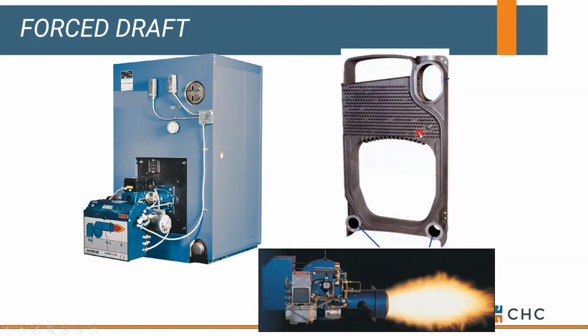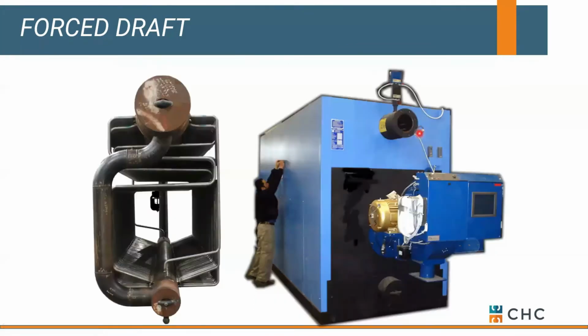You could take that same power burner and stick it into a steel tube design. So this is a good example of a bent tube or steel tube boiler. That hot flue gas is going right down the center, and then there's actually 5 passes before the flue gas leaves the boiler.